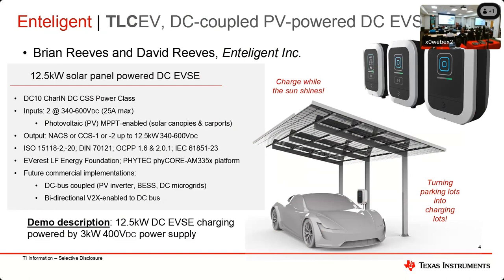In between, on that 400-volt bus, is the newest standard to charge 400-volt home batteries. Home batteries are going from a 48-volt standard to a 400-volt standard because they're more efficient. We would connect up to that same DC bus, so have our own terminal inputs. And in fact, I think the Delta inverter that's used with the Ford home energy integration system has a separate input for an EV charger connected to their DC bus.